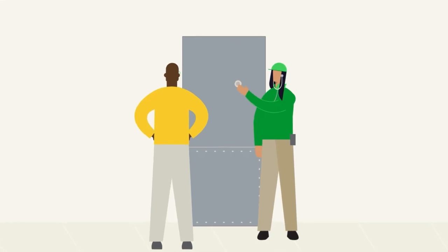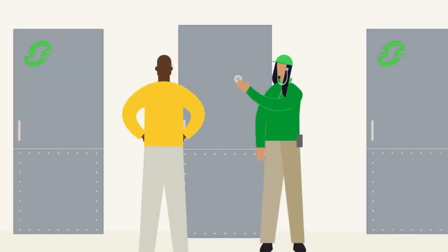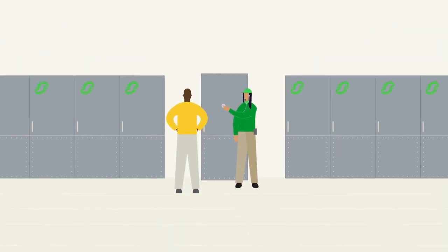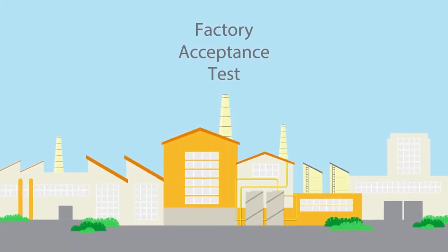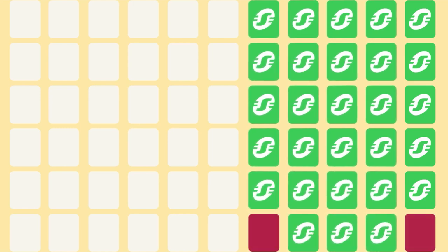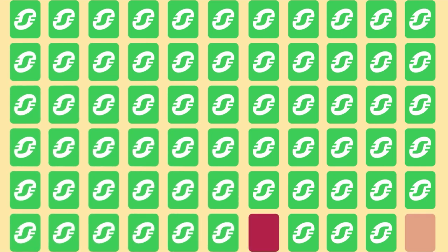Prior to startup, if you haven't used the external cabinet approach, there's a number of tests that need to be run. Actually, the process really begins at Schneider Electric. Once code conversion and loading onto new cards are complete, we do a pre-FAT or factory acceptance test ourselves, typically with you, our client, present. We'll spot test 10% of the cards. If any issues arise, we'll move to 50% testing. If any additional issues arise, we'll pre-test the entire batch. Once everything is working properly, we'll pack and ship it to your facility.